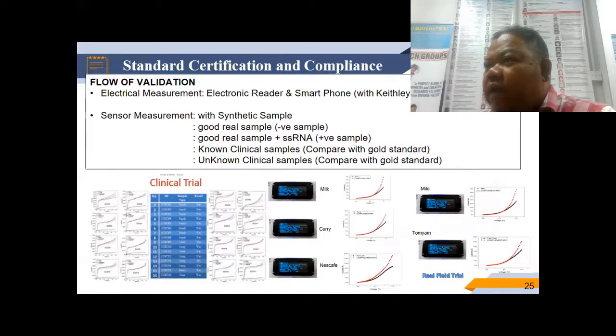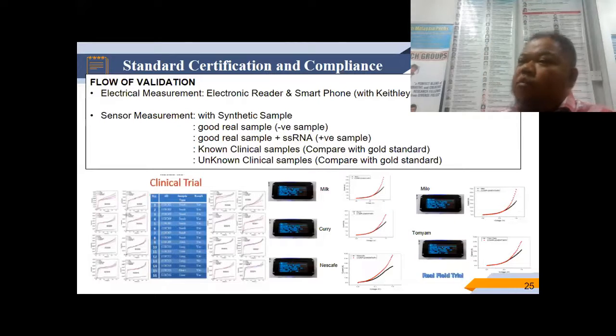So there are two types of validation that I have to do. One is for the system, the reader itself: electrical measurement, electronic reader plus smartphone. So I have to make sure, and then I compare with the Keithley, which is a gold standard, a standard electrical measurement. I have to compare whether they obtain the same result or not. So I start with this, and then followed by the sensor measurement.